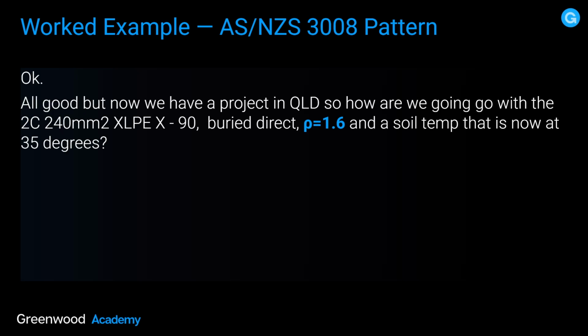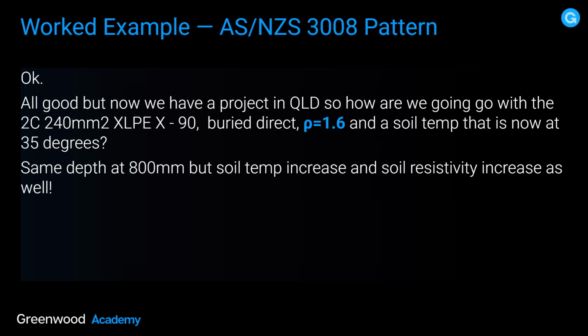So let's look at some other variations. All good. But now we have a project in Queensland. So how are we going to go with the 2-core 240mm XLPE X90 buried direct, but this time with a thermal resistivity of 1.6 and a soil temp that is now at 35 degrees. So we've increased our thermal resistivity of the soil. We've increased the soil temperature. How much of an effect is that going to have on the actual current carrying capacity of that same 240mm XLPE cable? Let's find out. We're talking the same depth at 800mm, but a soil temp increase and soil resistivity increase as well.